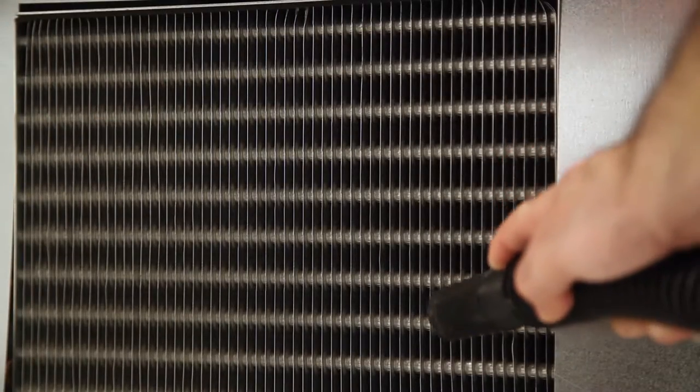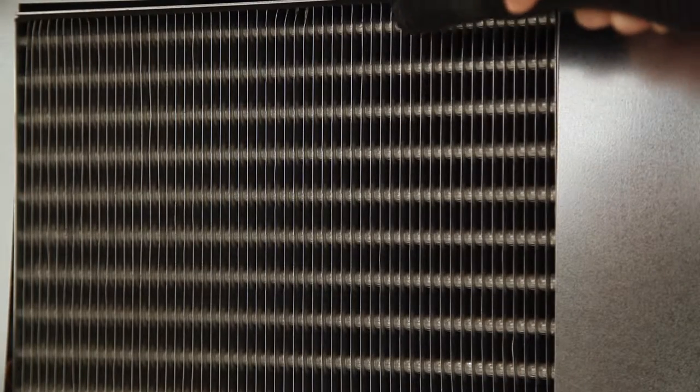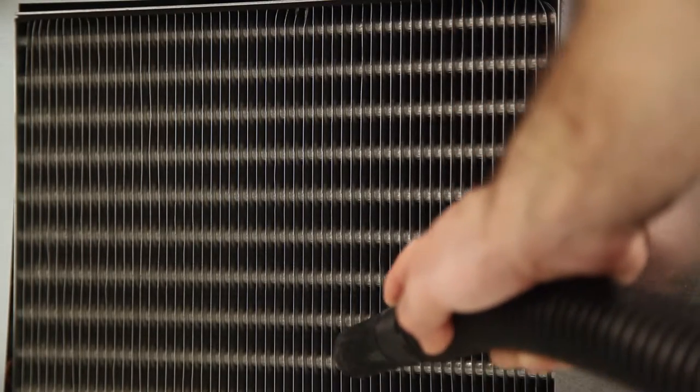After brushing the condenser coil, vacuum the dirt off the coil moving the vacuum up and down and never side to side as this could also bend the fins on the coil.